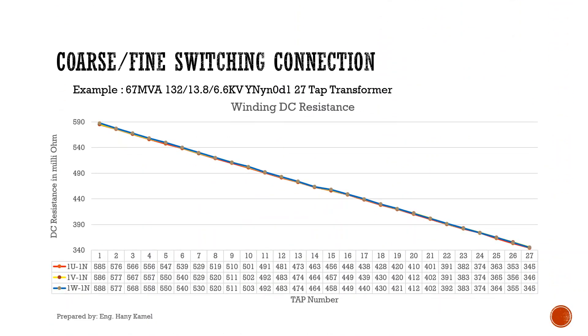For DC winding resistance, we have an example: a 67 MVA transformer, 132 over 13.8 over 6.6 kV, with vector group YNYN0D1 and 27 taps. The DC winding resistance is as shown in the curve. Tap number 1 has the highest value and tap number 27 has the lowest value.